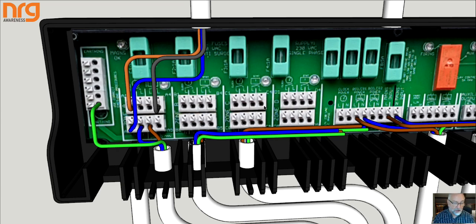4 is joined to 7 and 8 because look, 1, 2, 3, 4, 5, 6, 7 and 8. 4, 7 and 8 are joined together. If power comes into 4, it lights the LED. It energizes whatever's connected to any of the other 2 terminals. For example, in this scenario, it's onto the pump. And it also closes the boiler relay. So the 4 terminal in each block is the one that does all the work.